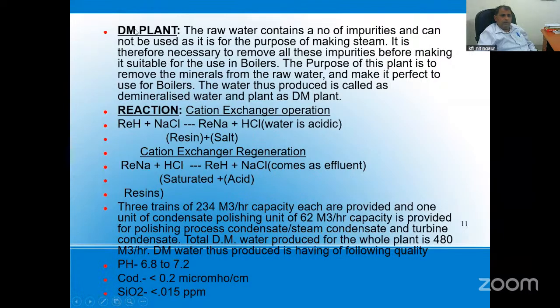So DM water is mandatory for the steam boiler. DM water is used only for making steam, and for other purposes we use the raw water directly, for the heat exchanger, cooling another fluid, with the help of the cooling tower. We cannot waste the water. We have a large number of cooling tower cells in the plants to cool down the water to the desired level. We can explain later.